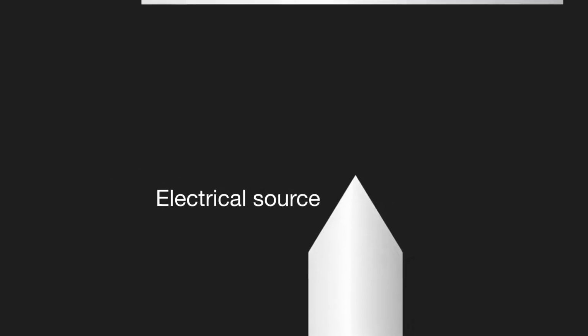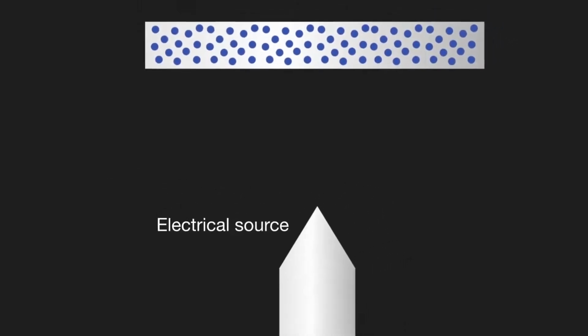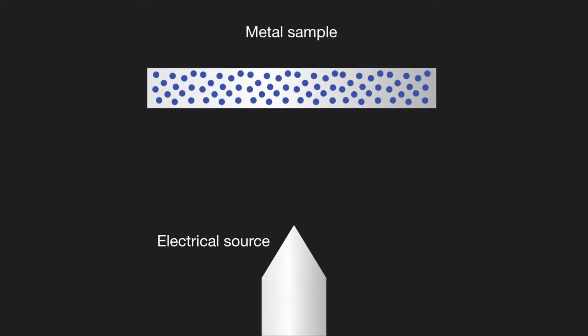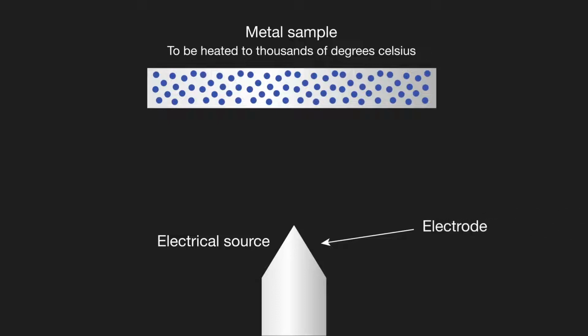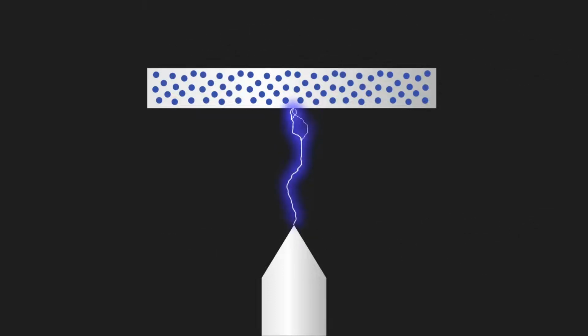All OES analyzers contain three major components. The first is an electrical source to excite atoms within a metallic sample so that they emit characteristic light or optical emission lines. This requires a small part of the sample to be heated up to thousands of degrees Celsius. This is done using an electrical high voltage source in the spectrometer via an electrode. The difference in electrical potential between the sample and electrode produces an electrical discharge. This discharge passes through the sample, heating and vaporizing the material at the surface and exciting the atoms of the material, which then emits the element characteristic emission lines.